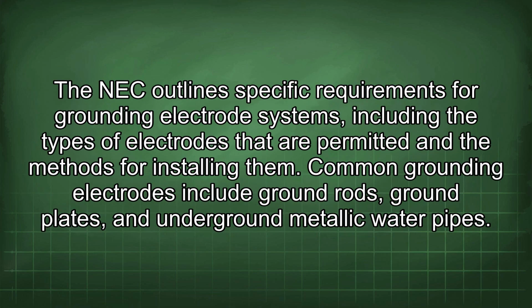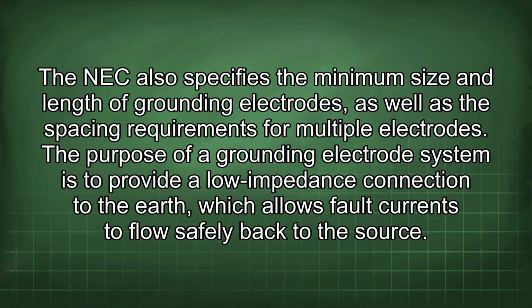The NEC outlines specific requirements for grounding electrode systems, including the types of electrodes that are permitted and the methods for installing them. Common grounding electrodes include ground rods, ground plates, and underground metallic water pipes. The NEC also specifies the minimum size and length of grounding electrodes, as well as the spacing requirements for multiple electrodes. The purpose of a grounding electrode system is to provide a low impedance connection to the earth, which allows fault currents to flow safely back to the source.